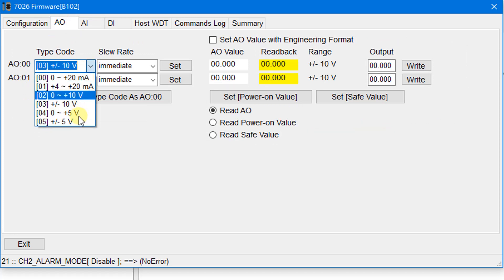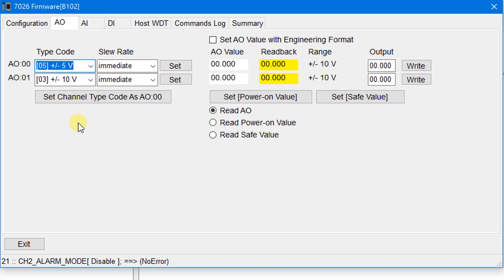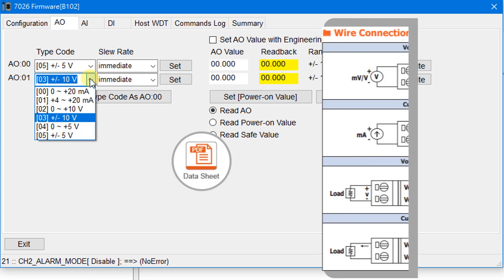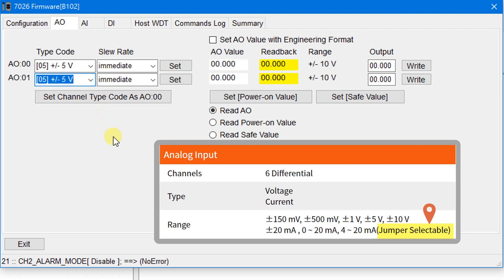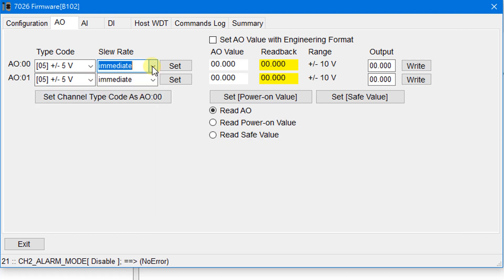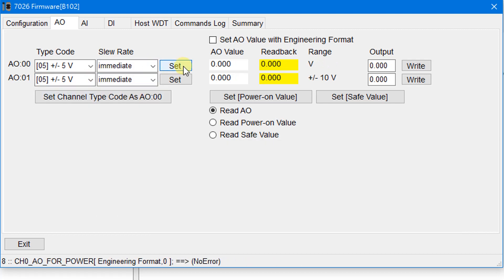First, set the type code to ±5 Volts. Most modules have internal jumpers that determine the type to be used. Before setting the type code, ensure that the jumpers are properly configured — you can find this information on the product page. Then click the Set button.